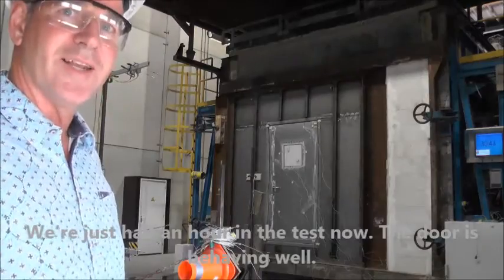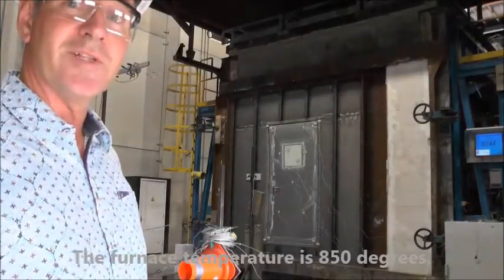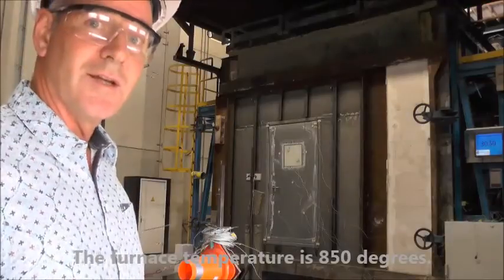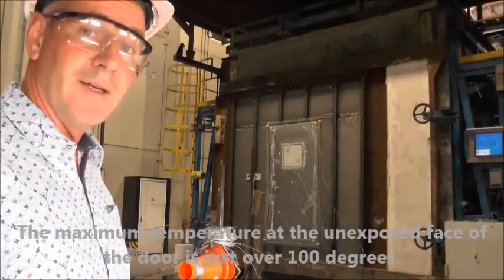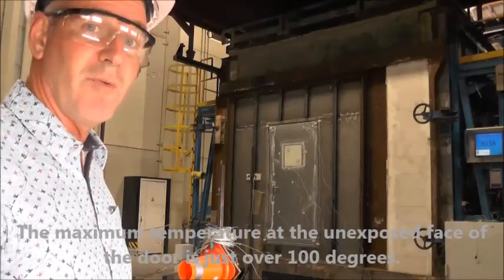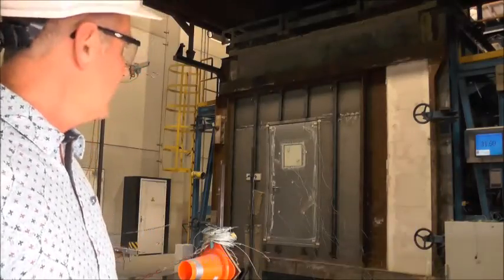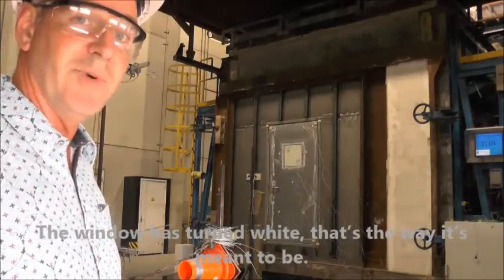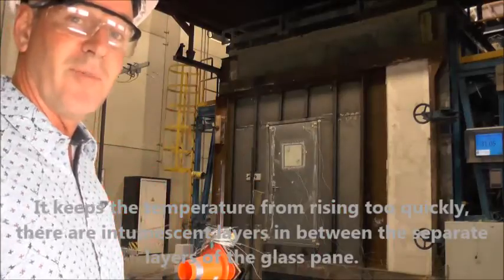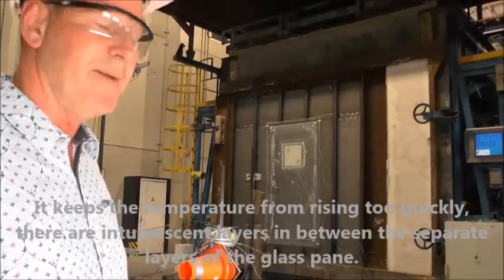We're just half an hour into the test now. The door is behaving well. The furnace temperature is 850 degrees, and the temperature on the unexposed face of the door is now just over 100 degrees, while the average temperature is much lower. The window has turned opaque — that's the way it's meant to be. It keeps the temperature from rising too quickly, thanks to intumescent layers between the separate layers of the glass.